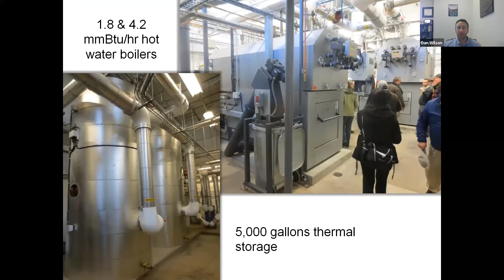I mentioned thermal storage tanks - that's one design aspect I want to talk a bit about. Whenever you have a hot water system using wood energy, you're pretty much always going to benefit from having a thermal storage tank as part of the integration into your facility. The tank is literally just a big tank full of hot water, but it's plumbed in a certain way that allows it to store energy at a hotter temperature than is delivered out to the district system or to the building.